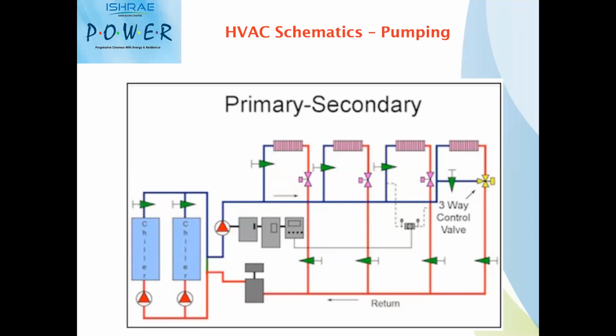When it is a cooling tower application, it is an open loop system where water has to be pumped from your condenser outlet to the cooling tower. So that particular vertical height needs to be kept in mind. But again, when the water is coming out of the cooling tower and coming back to the suction of the pump, that particular suction head is added. So the differential head, whatever is coming out of the condenser pump, will decide the head of the pump.